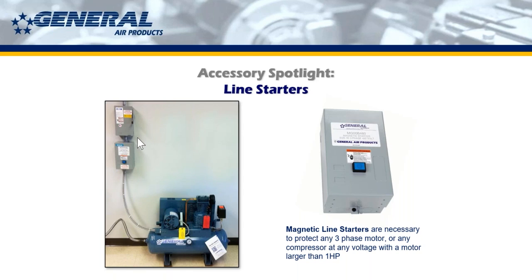The way the line starter works is when it senses high voltage, bad voltage, something going on that can damage the unit past it, it quickly cuts off power between it and that unit. And that blue button that you see on it is the reset button. So basically, power will remain off on that air compressor until the line starter button is pressed. When the line starter button gets pressed, then if the problem was, let's say, a lightning strike or whatever, the compressor should come back on, as long as the box wasn't fried.